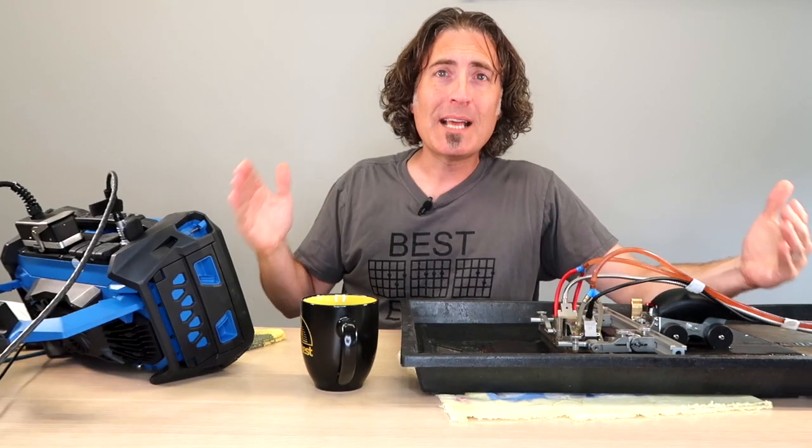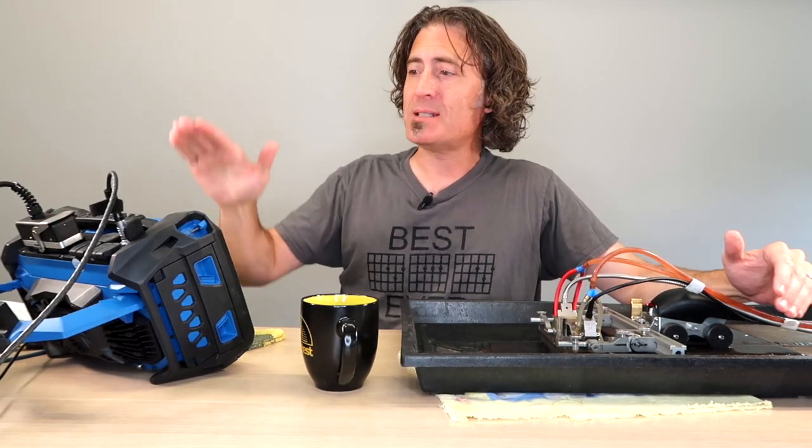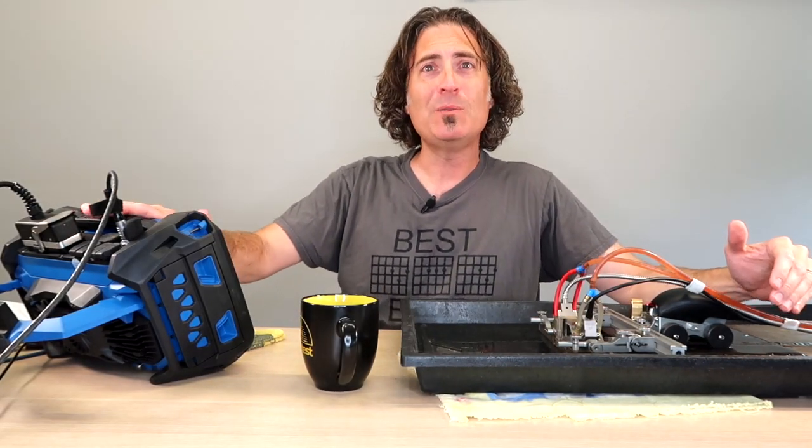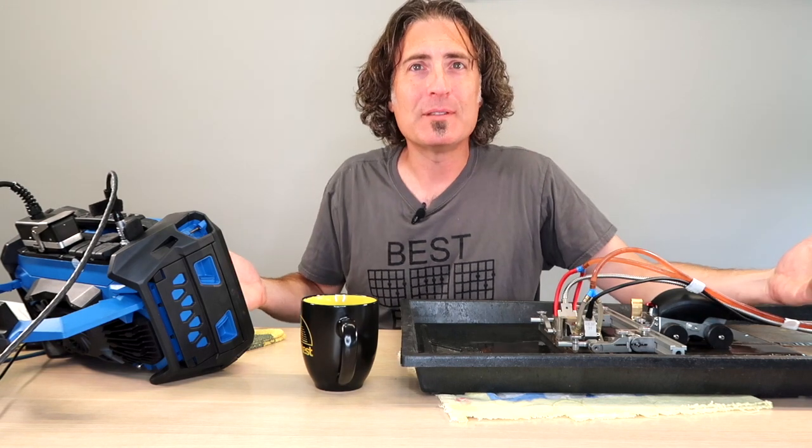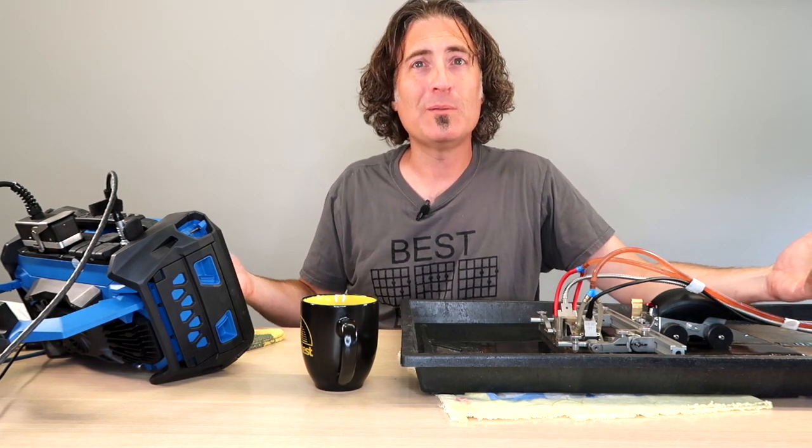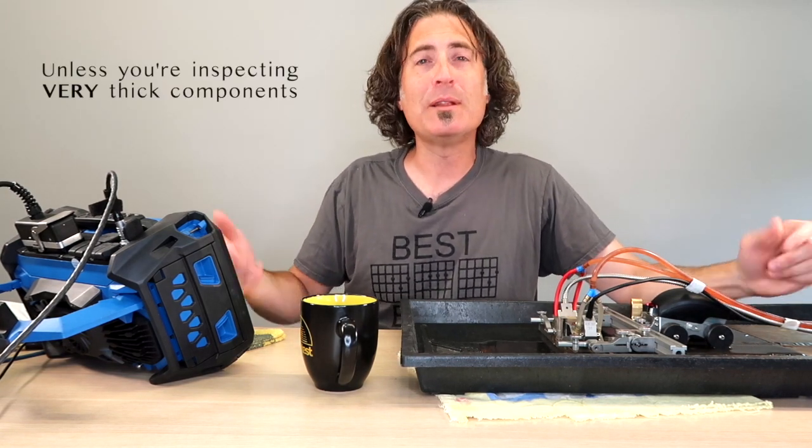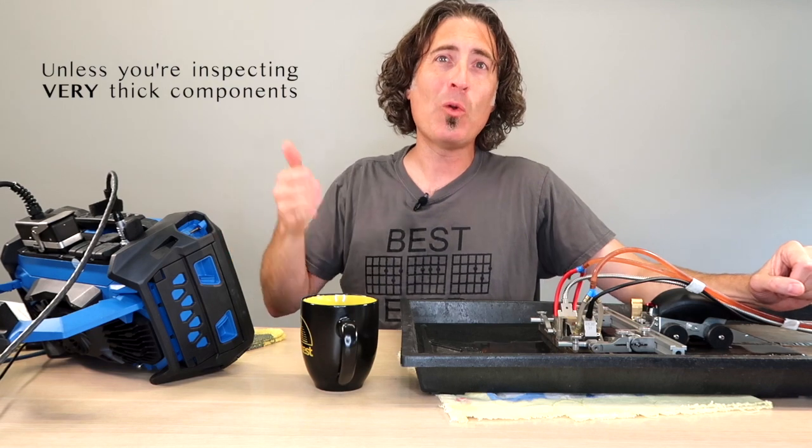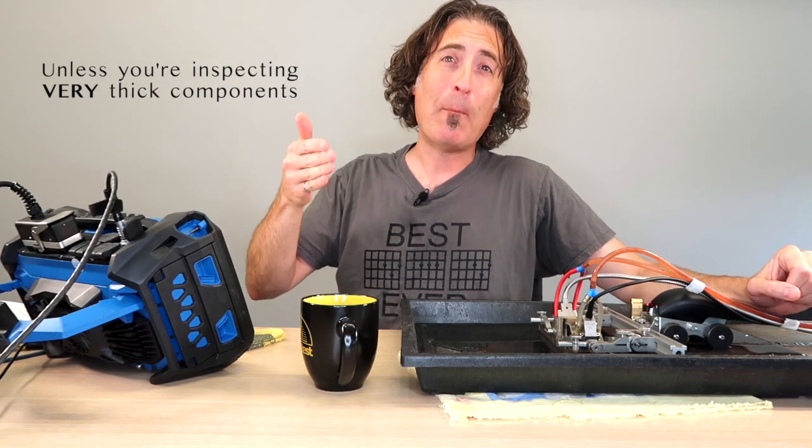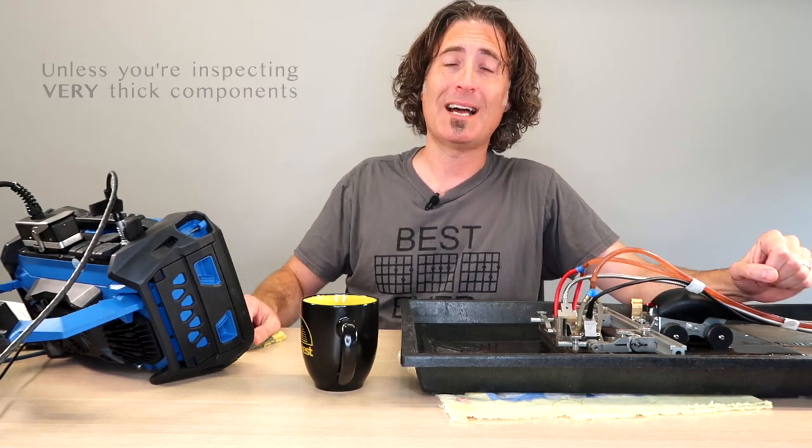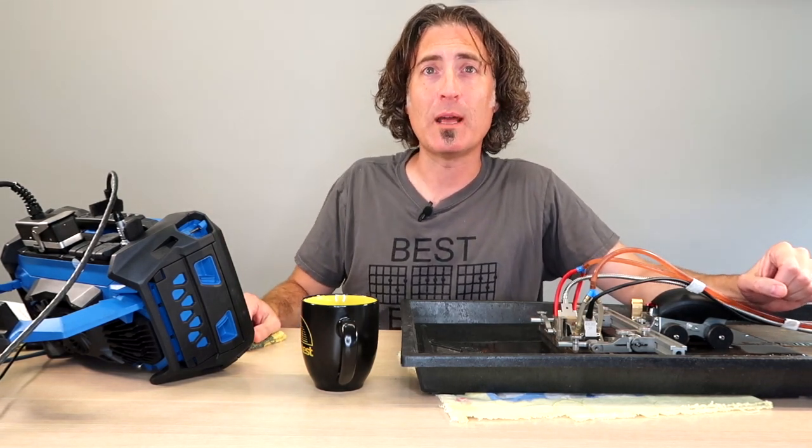For normal sound path ranges, sample at 100 megahertz, we just don't have 16,384 points. We have probably 2 or 3,000. That's normally going to be the maximum number you can ever dial your points quantity up to.